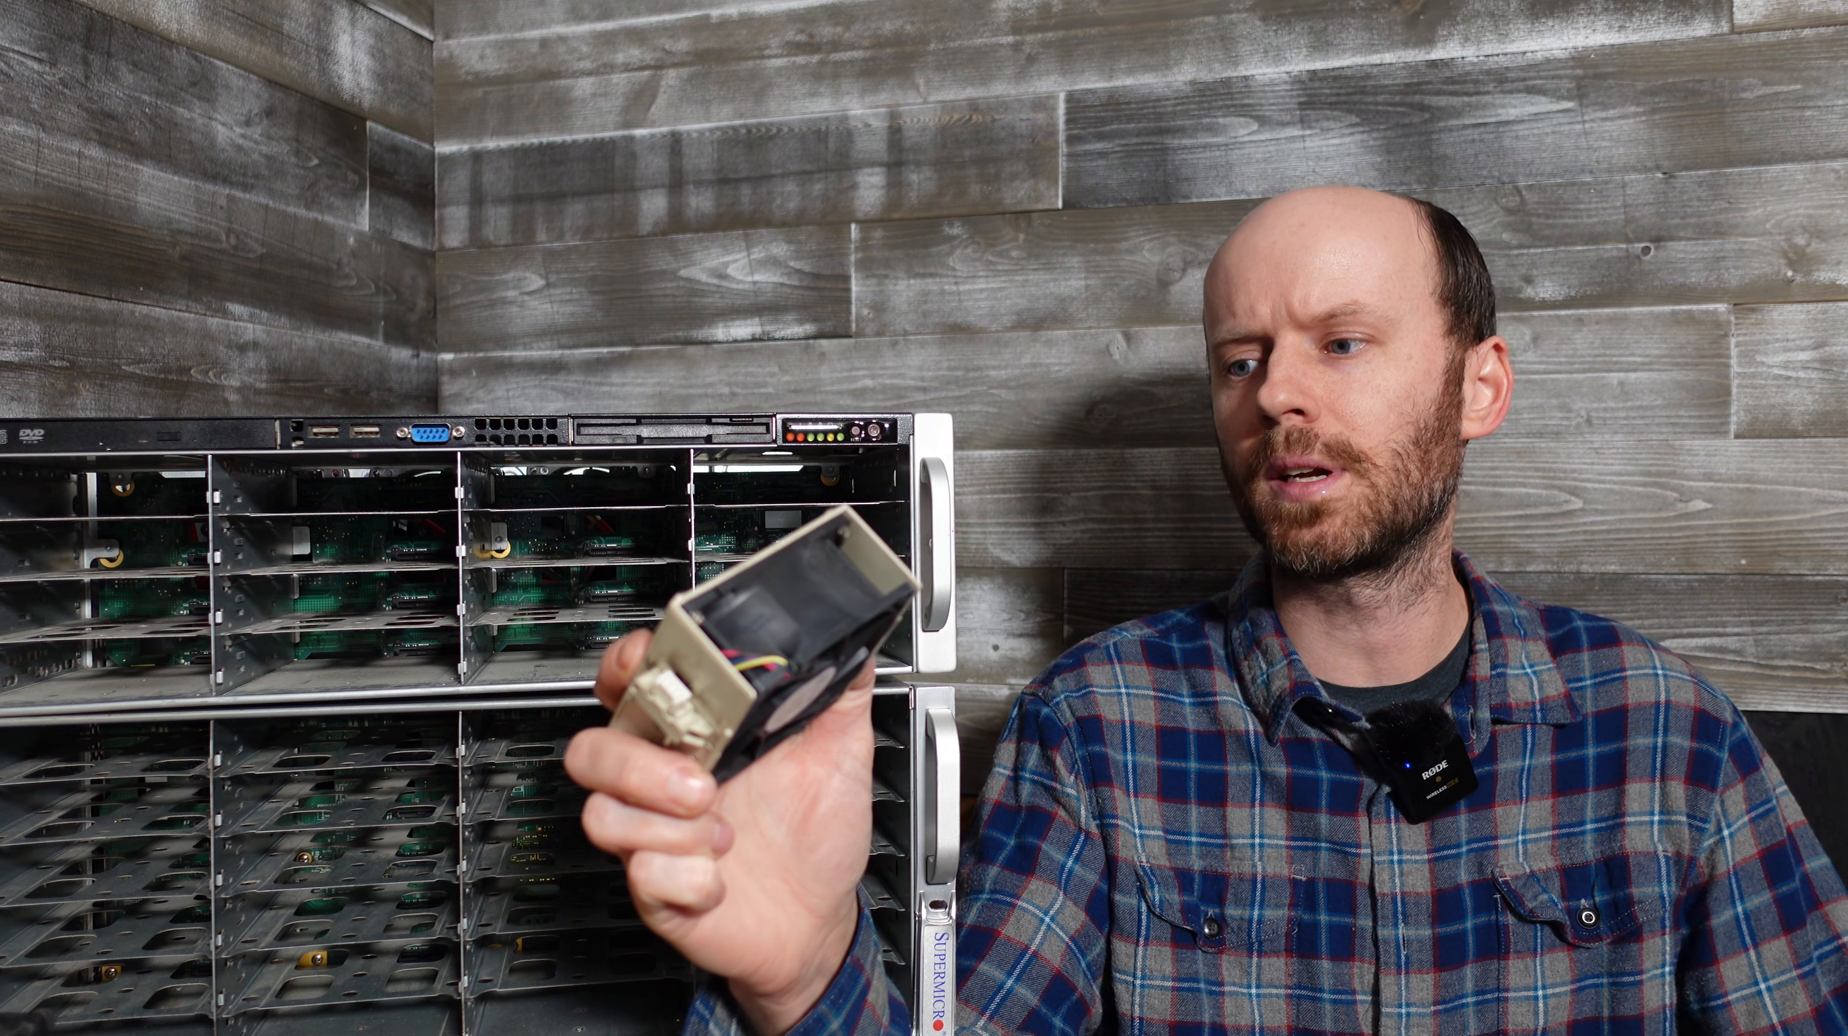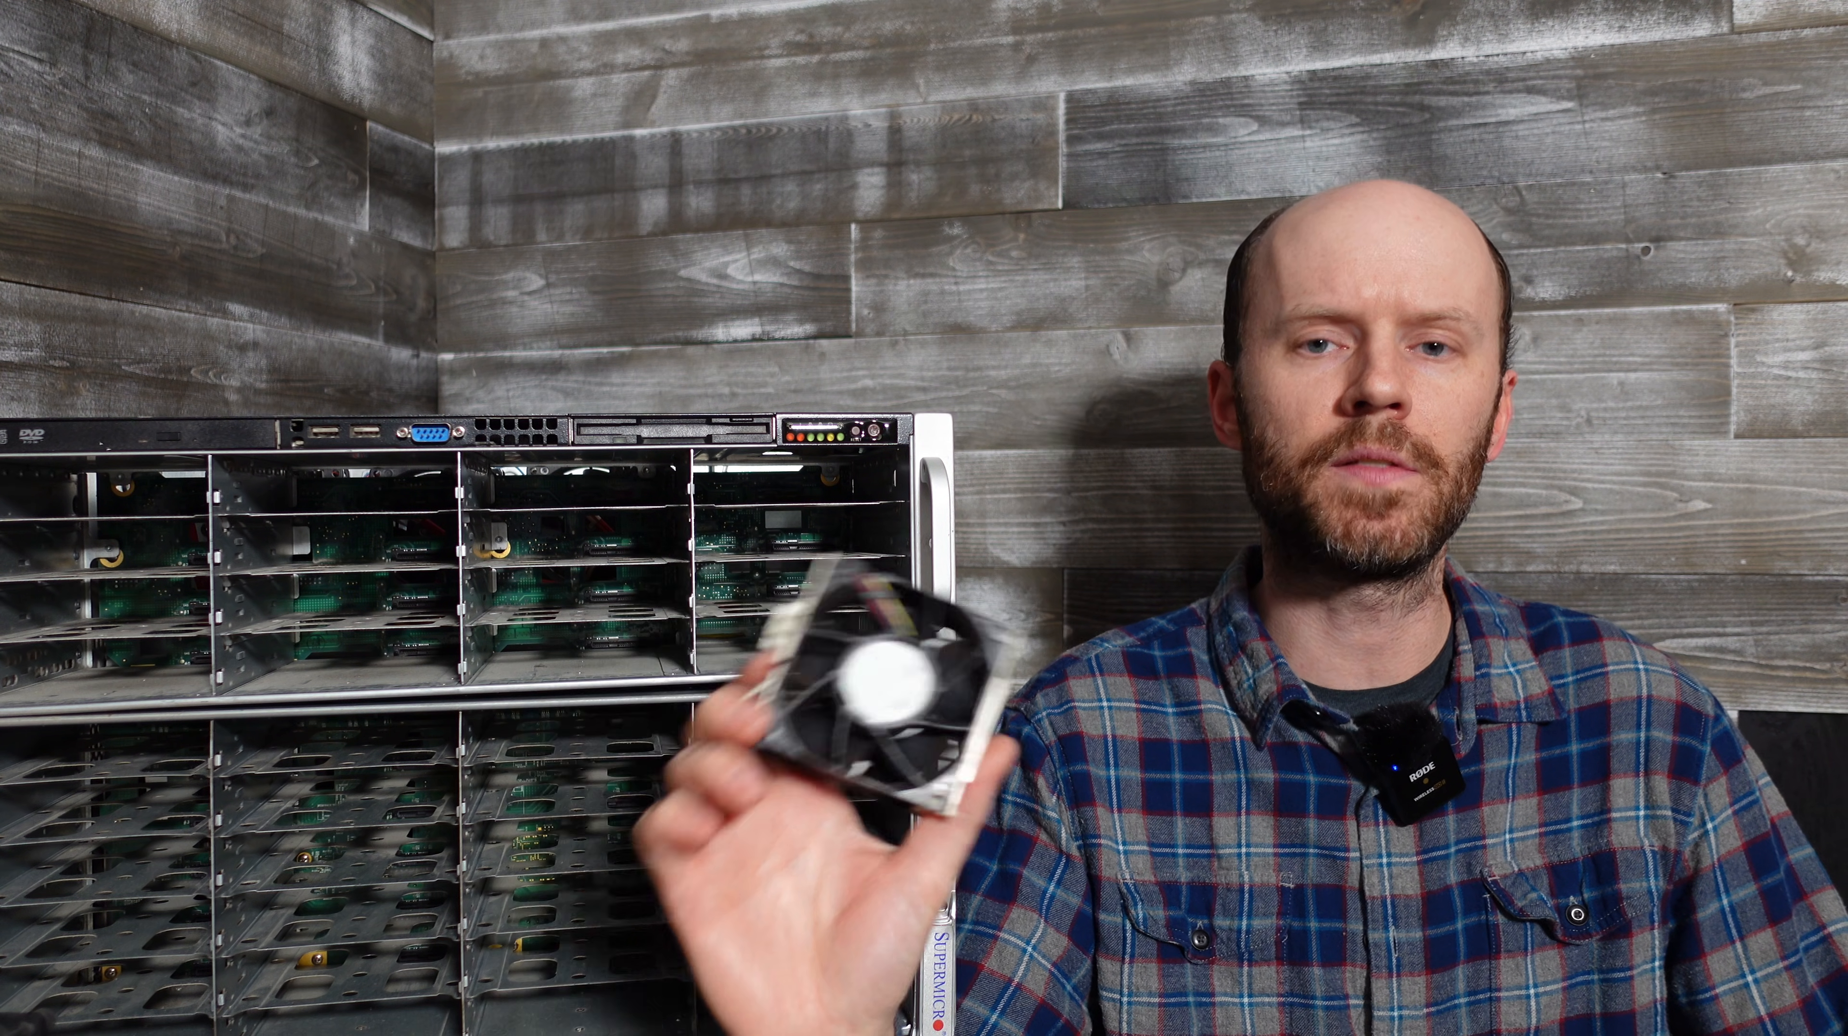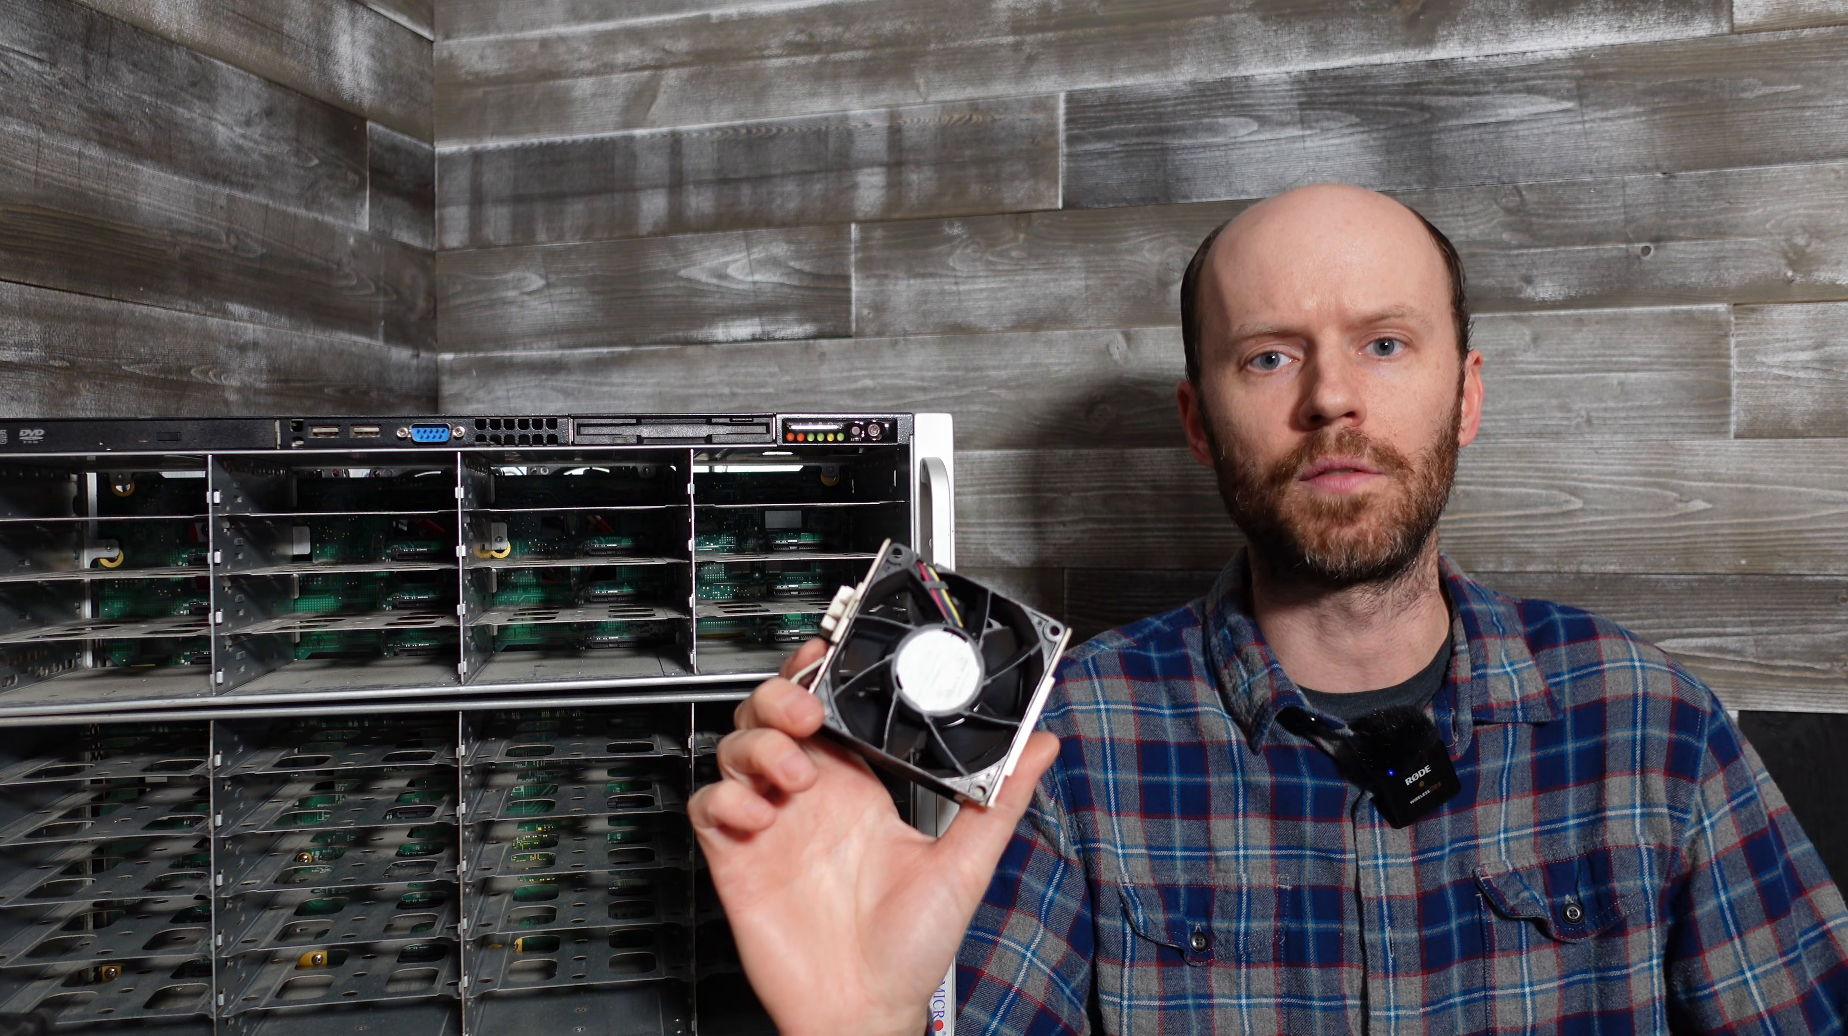These are the original fans I pulled out. They are part number 0126L4. They are rated for 7,000 RPMs, approximately 72 CFMs, and a static pressure of 1.09 inches of water.